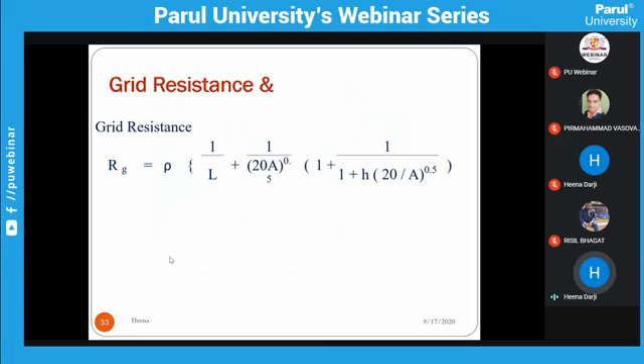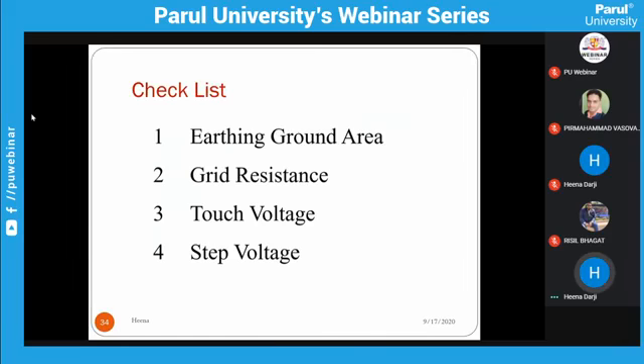Now, the main important thing is grid resistance. We always have to maintain grid resistance below 1 ohm, so that we can live in the substation. So we have to maintain this grid resistance, RG, below 1 ohm. Now we have to check these four main things. The earthing ground area must be more than the required area, meaning the materials area. Grid resistance must always be below 1 ohm. Touch voltage must be less than the calculated touch voltage, and step voltage must be less than the materials step voltage.